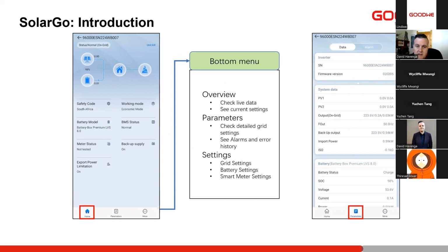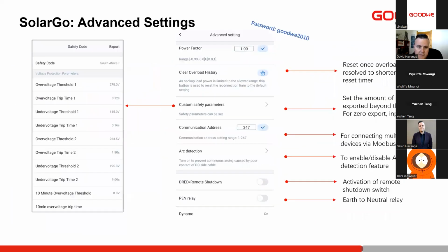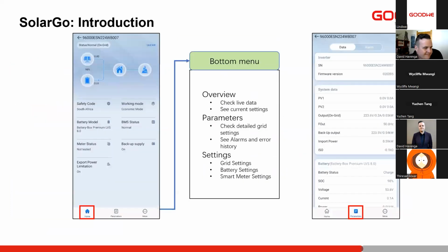In the parameters, you'll find a lot more in-depth information about the device, such as the serial number, the firmware version on the device, the PV voltage inputs and currents, grid voltage inputs and currents, the backup output voltage, and all that information. Here's where you can check all your voltages and make sure that everything is correct.